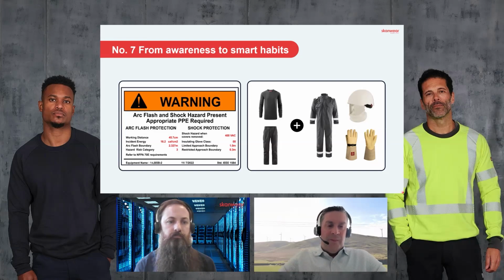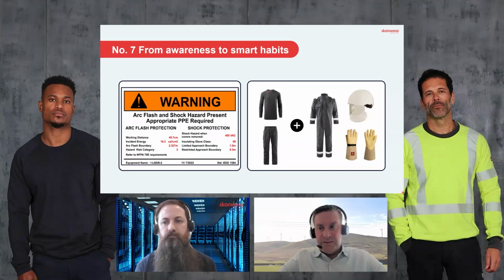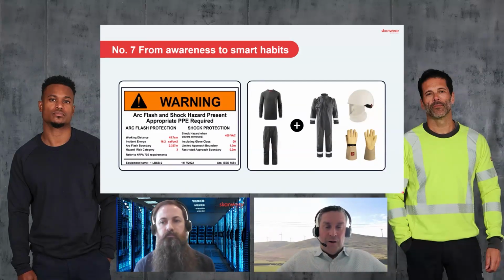So if, for example, the incident energy was 12 cal rather than 16 cal, the hazard risk category would tell you to be in a category 3 PPE. Category 3 PPE is 25 cal and upwards. It's a lot heavier than a 12 cal garment would be. So you might have a 12 cal label, wearing 12 cal top and bottoms and a 12 cal visor and balaclava or a hood, which would be a lot lighter weight and easier to wear than a 25 cal category 3 PPE product would be. So understanding what the incident energy is critical in making sure the right PPE is selected, and obviously then also giving you the shock protection there as well as needed.